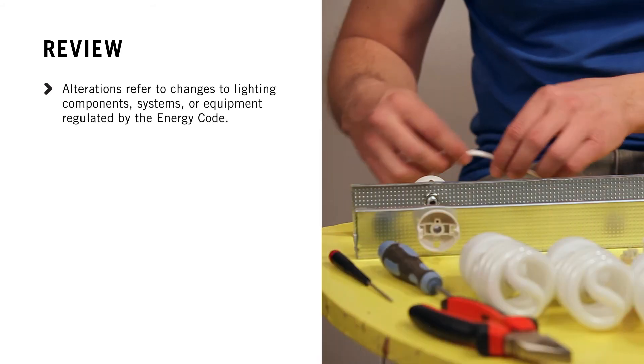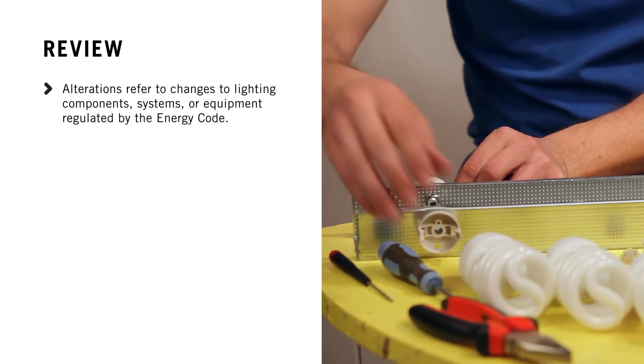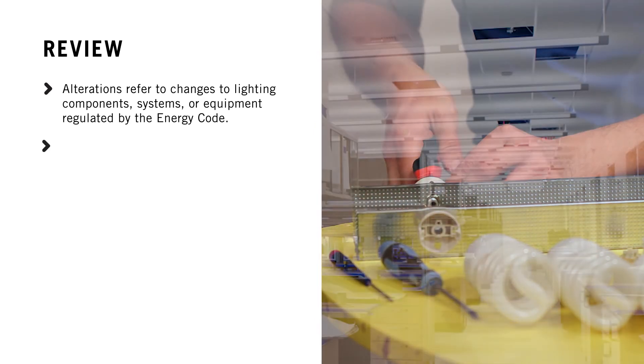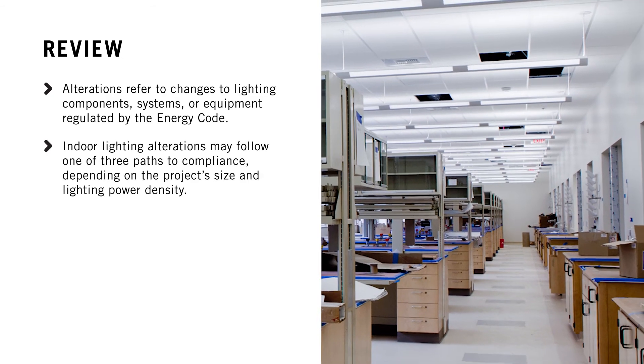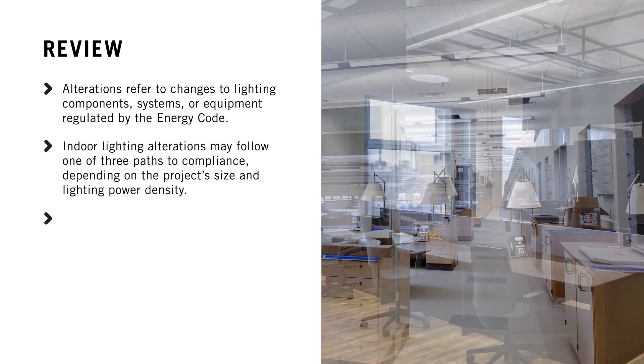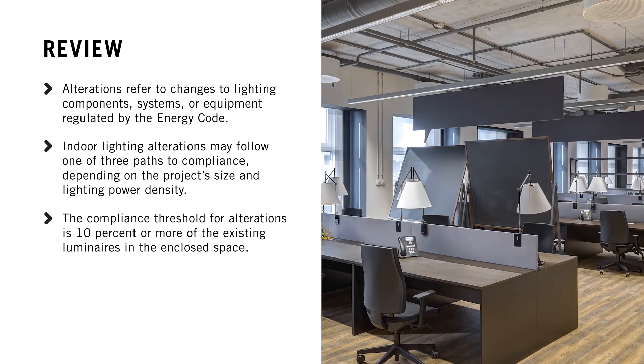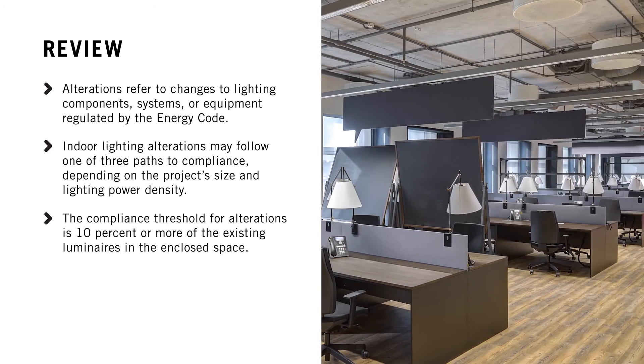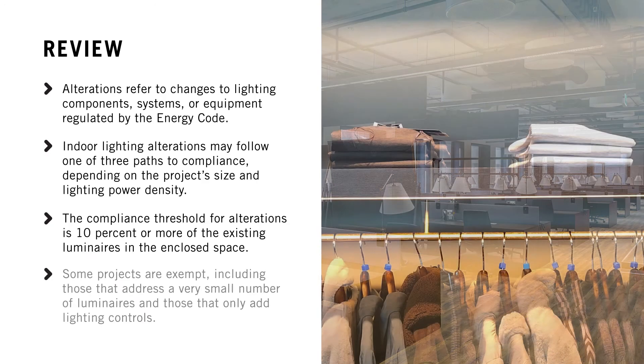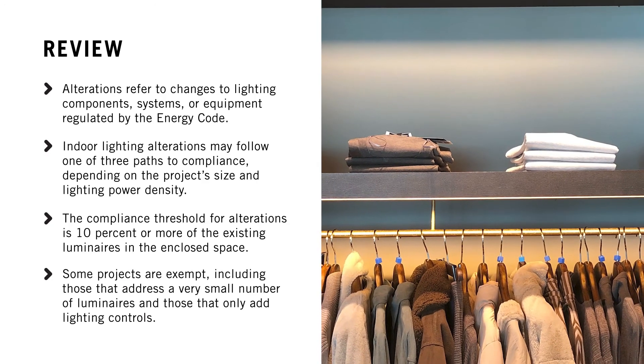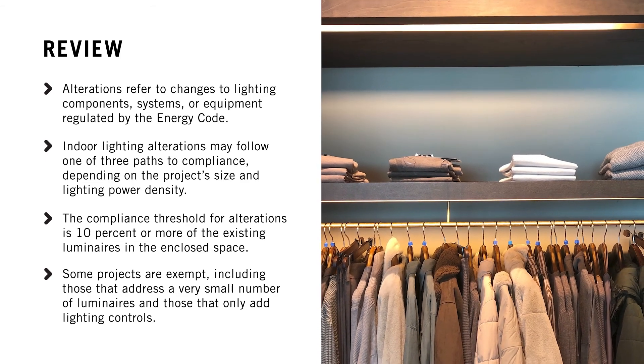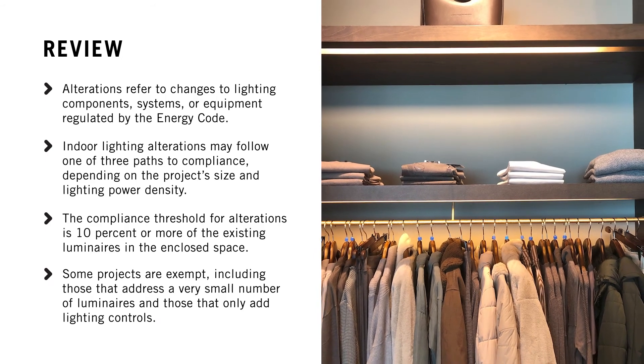Indoor lighting alterations refer to changes to lighting components, systems, or equipment regulated by the Energy Code. Indoor lighting alterations have three paths to compliance. The compliance threshold for alterations is 10% or more of the existing luminaires in the enclosed space. And some projects are exempt, including those that address a very small number of luminaires and those that only add lighting controls.